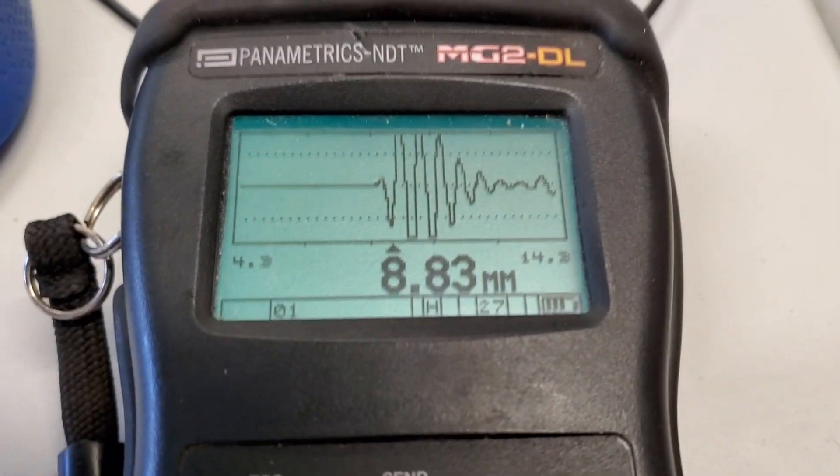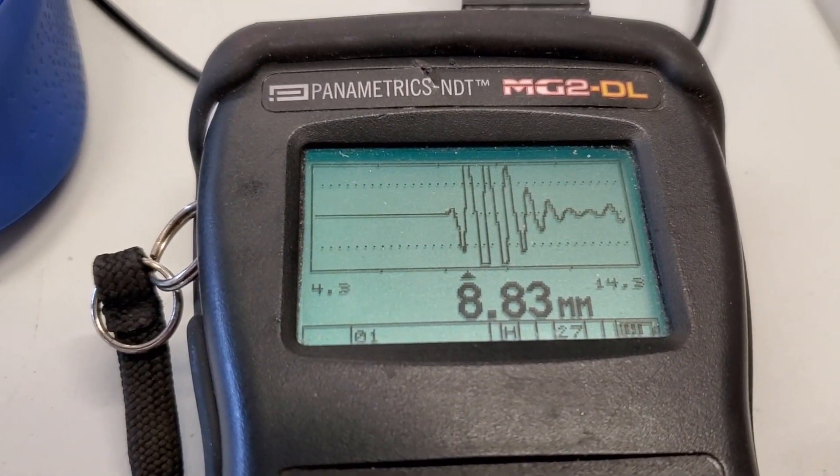If you have a thickness gauge, you don't have any choice. You have to let it do what it wants to do, and what it usually wants to do is pick a zero crossing point from a negative to a positive lobe. Now that works really well in a lot of cases, but you really have to keep your eye on the A-scan — though that's not really all that different from what you do on a flaw detector. Using a 2¼ and a 5 MHz probe as examples, let's take a look at a couple of the problems that can happen depending on whether you use edge or peak mode.